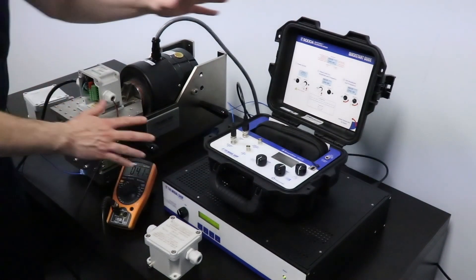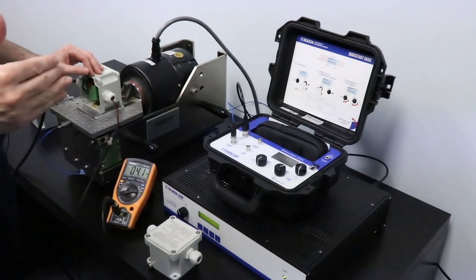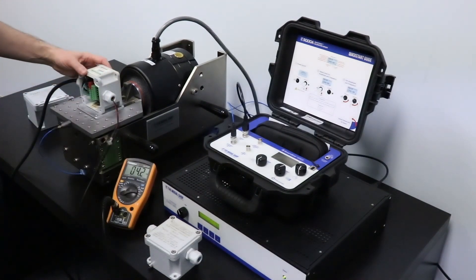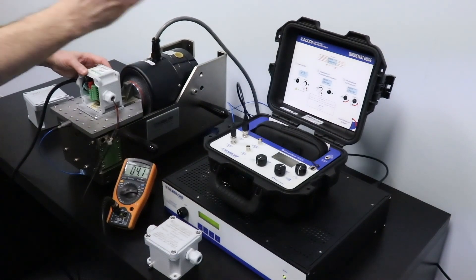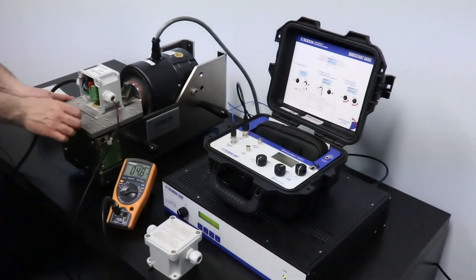I'm going to test the switches at different amplitude levels. So these are velocity switches. So I'm going to test it at different velocity levels. And I'm going to be using a little accelerometer mounted on the shaker table that's going to monitor how much vibration I'm getting out of the table.